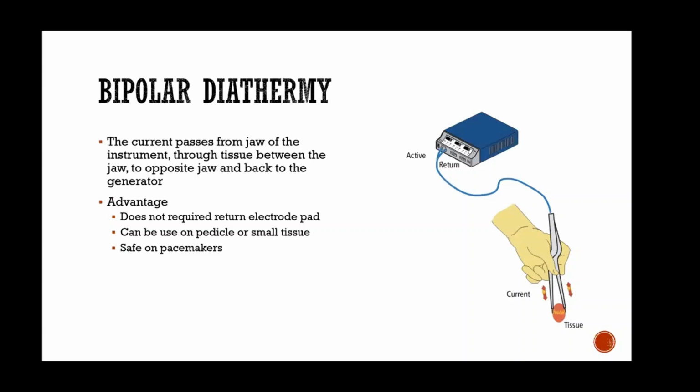It just passes from one jaw of the handheld device to the tissue between the jaws, then to the opposite jaw, and then back to the generator.